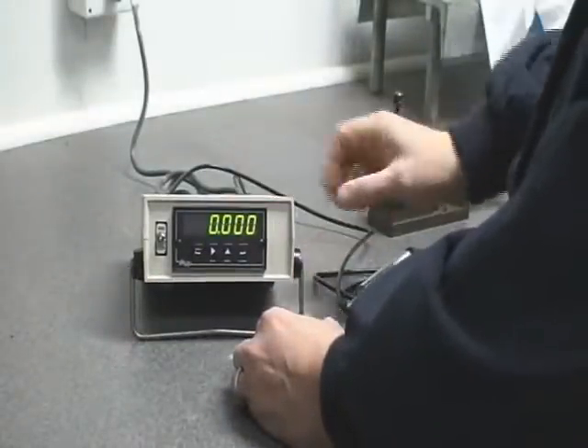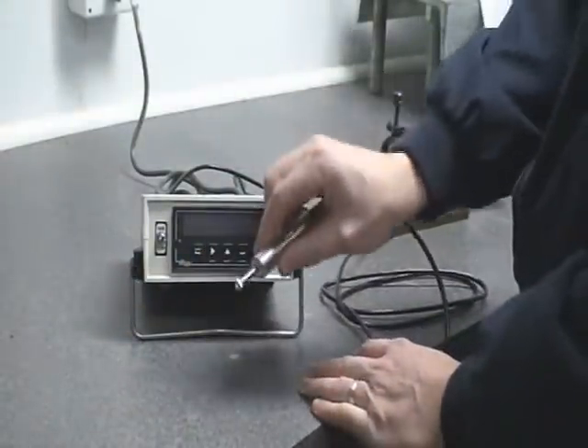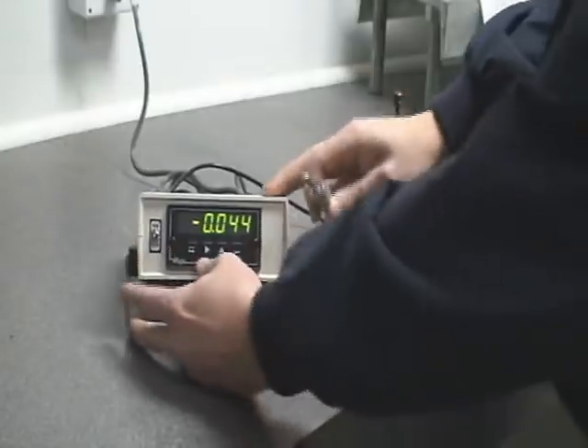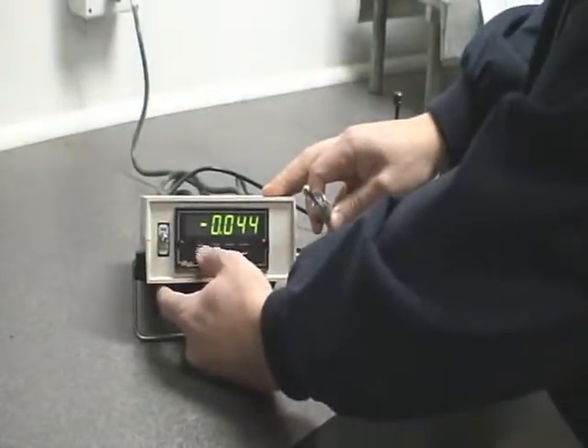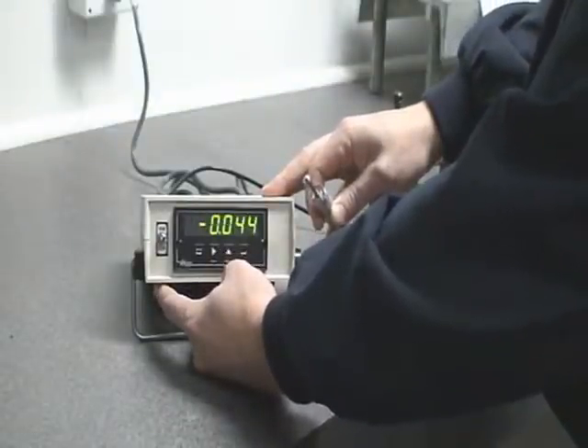I've got a one inch LVDT and now I want to capture my low end, which would be not flexed at all. Hit the menu, so you see low end, hit the peak and then hit the reset button — that stores your low read.